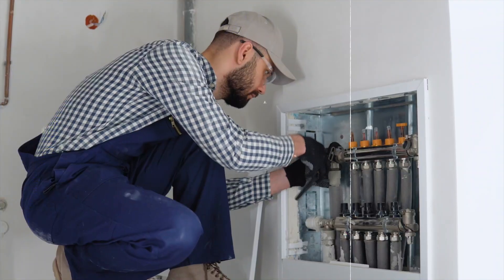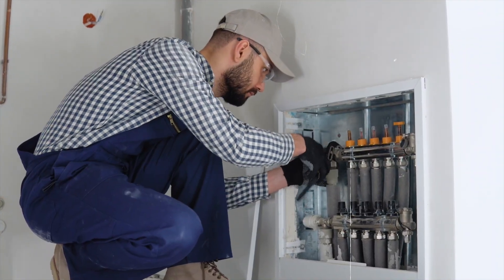One bonus component specifically for high efficiency systems is a low loss header with a built-in air eliminator. The reason these are great is that they ensure your delta-T between your primary and secondary loop is sized properly for your boiler, and they do an excellent job of air elimination, making sure your system functions efficiently. These are definitely an added expense, but we include one on every single one of our boiler install bids for that reason.